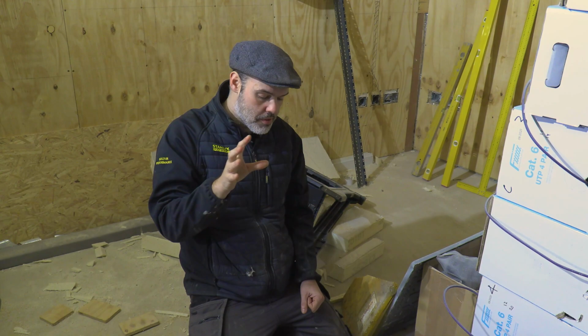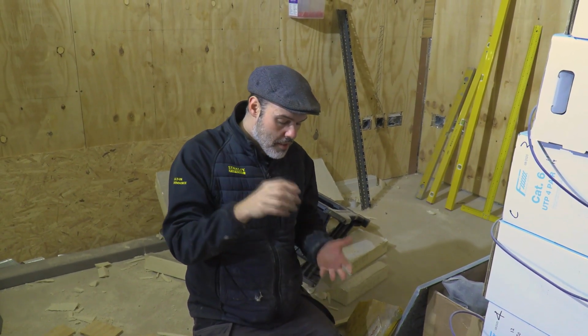I don't think these systems are actually fantastic, but they are required by the building regs. But if your float switch were to break or something like that, and of course this float switch is never going to engage except for 15 years down the line. Got it. So you're never going to know. This is the alarm float switch we're talking about, rather than one that's been in and out. So it's sat there for 15 years and seized, say. Absolutely. You'd never know if it works or not, unless you have to test it.